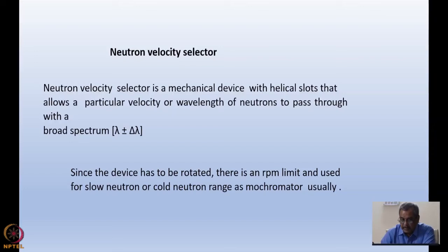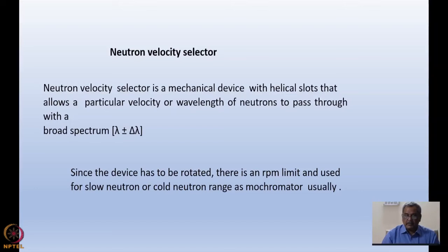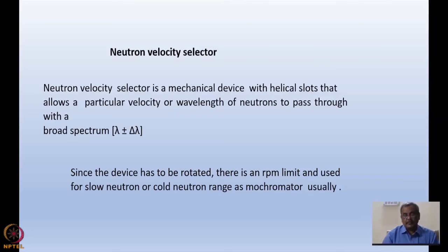The next device is the neutron velocity selector. It does not chop the beam but rather selects a wide monochromatic band from a given polychromatic beam, so it can be used as a monochromator even in a continuous source. Since we have to rotate this device, there is a limit on rotations per minute, and it is preferable when we want slow neutrons or cold neutrons - making it good for spectrometers using cold neutrons.